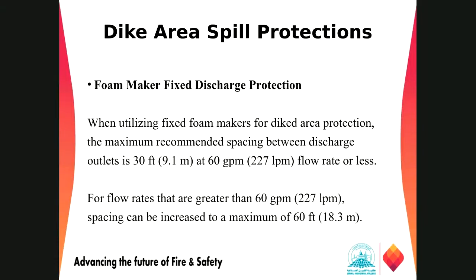So when utilizing fixed foam makers for dike area protection, the maximum recommended spacing between discharge outlets is 9.1 meters at 60 GPM flow rate or less, or 18.3 meters or 60 feet for flow rate more than 60 GPM.